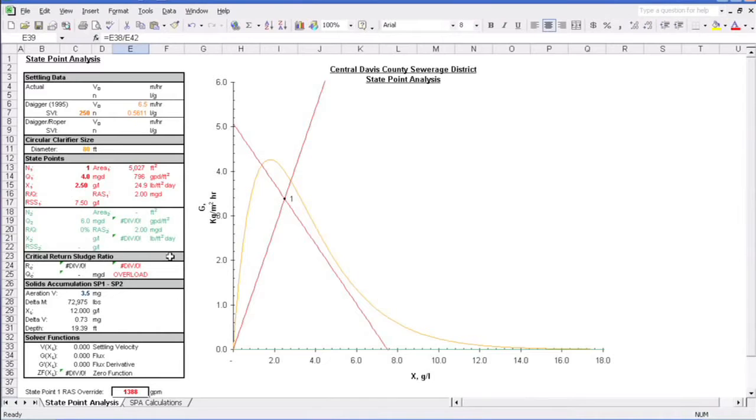But what would happen if flows continued to rise? Let's say to 5MGD. Well, in that case, we'd be failing in clarification as well as in thickening. Also, as mentioned, we've already maxed out our RAS pumps, so we can't pump any more out of the clarifier. In this scenario, there are two options.